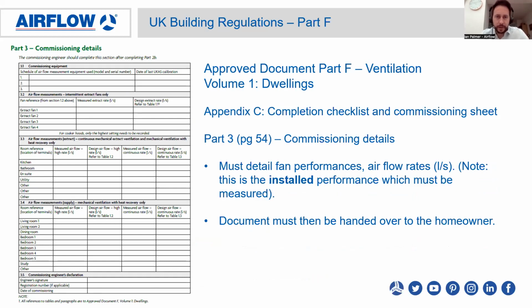Still on Part F, and skipping right through now to the appendix, there's a completion checklist and commissioning sheet right at the end. It gives all commissioning details, and this sheet must detail the fan performance, so the airflow rates in litres a second, and this is the installed performance which must be measured. Although manufacturers will put the performance of the fan on their data sheets, this could differ from the installed performance, because a lot of the time the performance of these fans is measured just for a wall. So if you're adding ducting onto the system, this adds pressure, and that installed performance could be affected. And at the end, this document must then be handed over to the homeowner. So all homeowners must be given a document that shows their ventilation rates in their home.